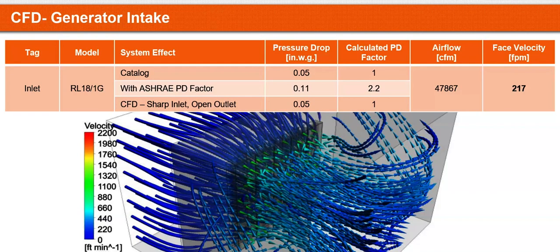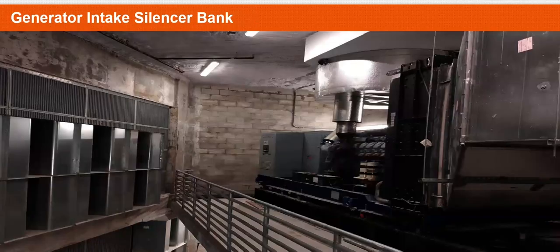But if all of a sudden you pressurize a room with a quarter of an inch, a third of an inch, and somebody's trying to leave the room during an emergency, and you're not able to open the door, that's going to be a big problem. So, another reason why paying attention to the size of these comes in handy, even as people might try to exit through the doors of that space. So, a couple of pictures of an outside plenum installation. You can see how big the openings are.